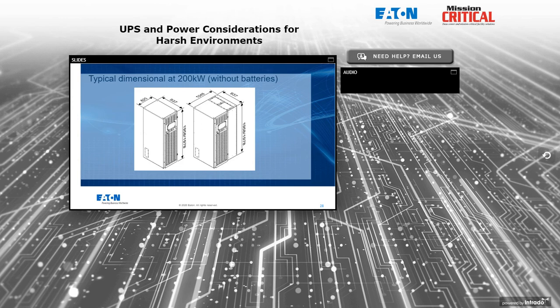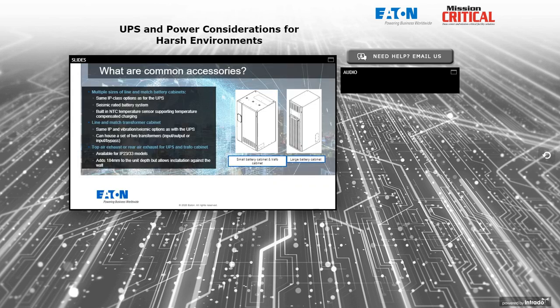So here's a set of typical dimensions in handy millimeters. Like I said on the previous slide, about the size of a refrigerator. Common accessories, same as for the mid-size UPS: seismic rated battery cabinets, built-in temperature sensing, or use that temperature and humidity sensor we mentioned before. Transformer cabinets for the input, output, and/or bypass that line and match with the UPS, and availability of higher IP rated cabinet construction.